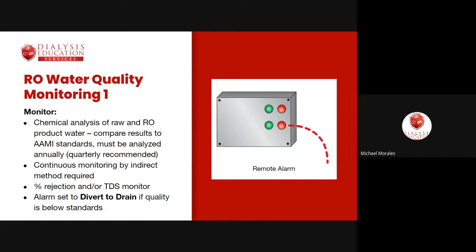At least annually, a full chemical analysis is performed on both raw/feed water and product water — samples are sent to the lab for a complete panel including potassium, calcium, sodium, and more. Quarterly testing is recommended but not mandated. Continuous monitoring combines direct daily testing with indirect monitoring — reviewing patient blood work and symptoms for clues about water quality.